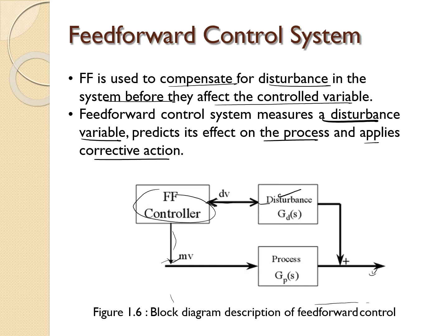Please remember that just now for feedback, we measured the process output, right? The liquid out, and then we regulated the steam in. So for feed forward, the control objective is to take corrective action for the disturbances, which are the temperature of the incoming liquid and the flow rate of the incoming liquid. So here, the sensor is at the disturbance side. In this system, we identify two disturbances, which are the temperature of the incoming liquid and also the flow rate.